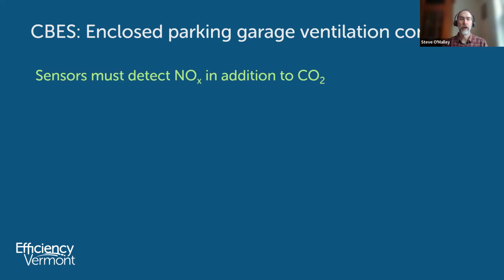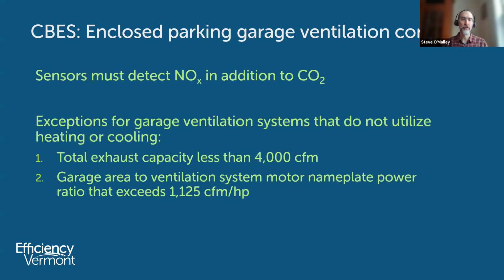Okay, enclosed parking garage ventilation controls. Previously, in the 2020 code, you had to monitor for carbon dioxide. Now the sensors must detect nitrous oxides as well. And there are some exceptions for garage ventilation systems that are unconditioned. If you have an unconditioned garage and the total exhaust is less than 4,000 CFM, then you don't have to have demand controlled ventilation in your garage.